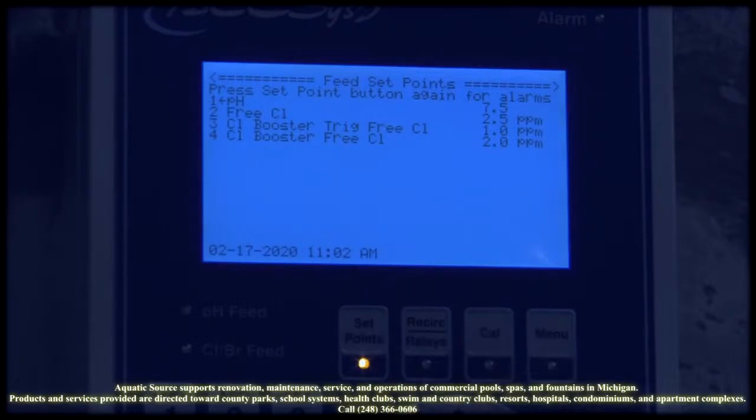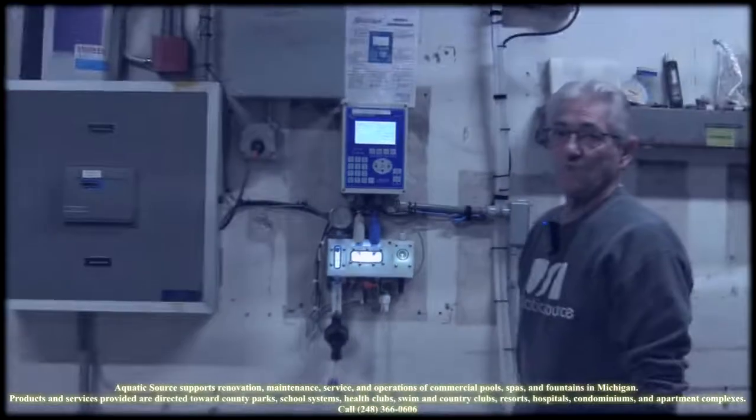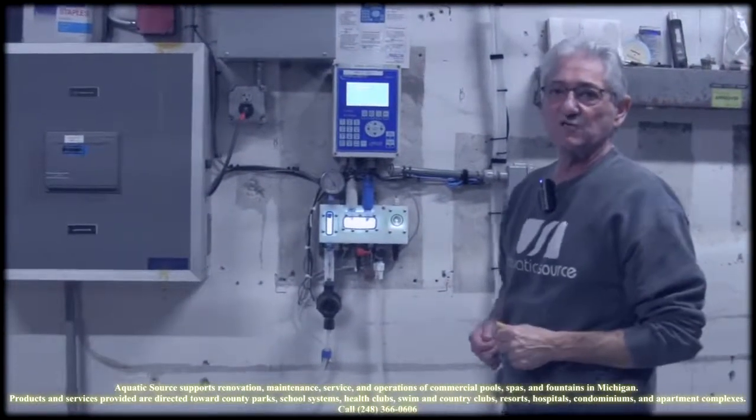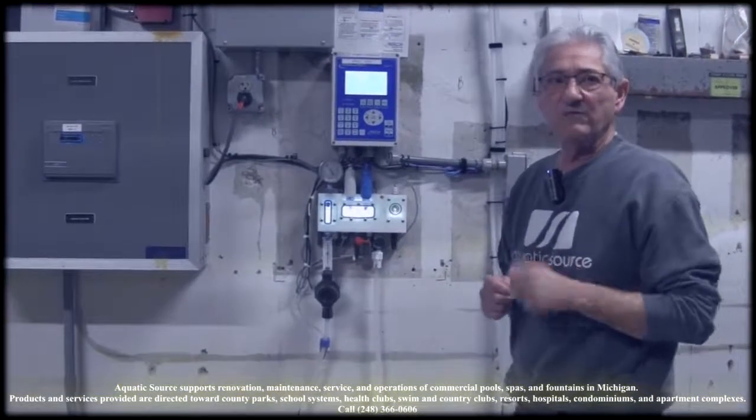Normal cleanings on these, or what you need to do to maintain it, is periodically you need to pull out your probes by shutting off the flow to it. You would turn the power off to the unit, unthread your ORP and your pH probe. You can take a solution of Dawn dish soap or any soap, dip the tip of it in, and use a toothbrush to remove any oil.